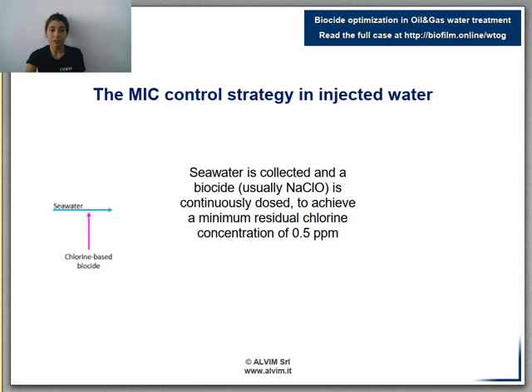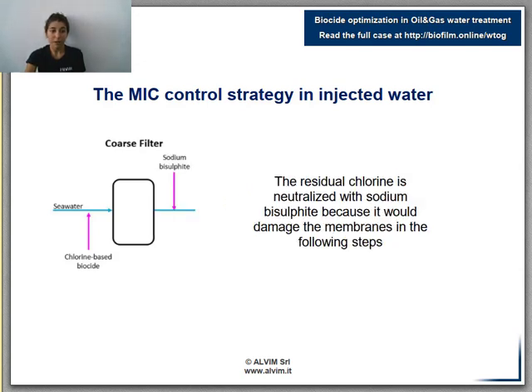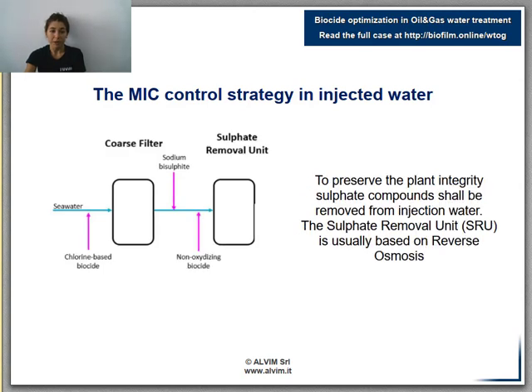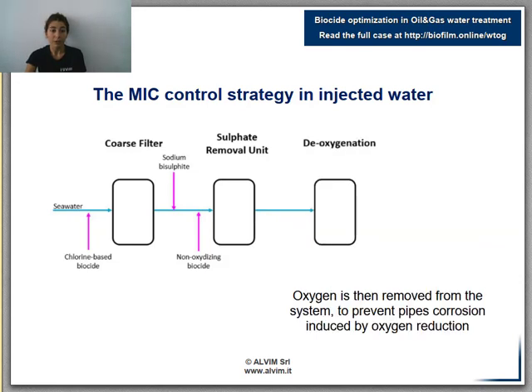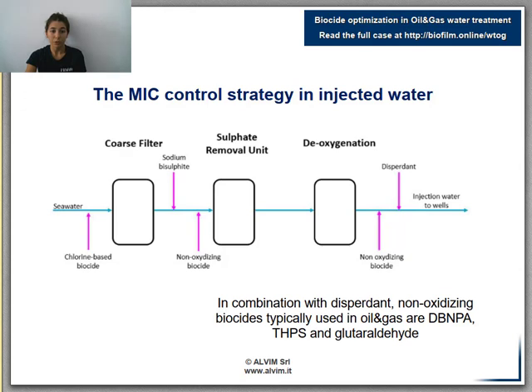First, seawater is collected and biocide is continuously dosed. Then filtration is needed to remove solids. Seawater must be neutralized, and it is recommended to eliminate sulfate ions from injected water — a reverse osmosis treatment is applied for this. The presence of oxygen is also very dangerous because of steel corrosion, so in the deaerator, oxygen is removed. Here the development of anaerobic bacteria is very likely, so a non-oxidizing biocide is dosed. In oil and gas industries, the most used are DBNPA, THPS, and glutaraldehyde, together with dispersants. Finally, seawater has been properly treated and can be injected into wells.